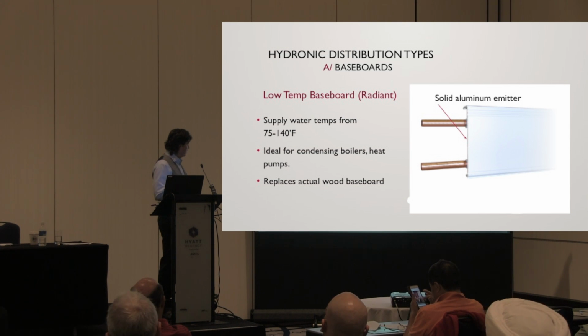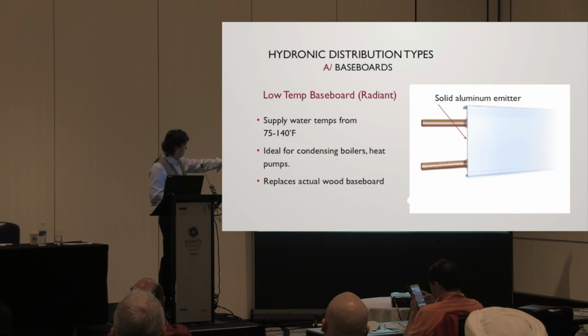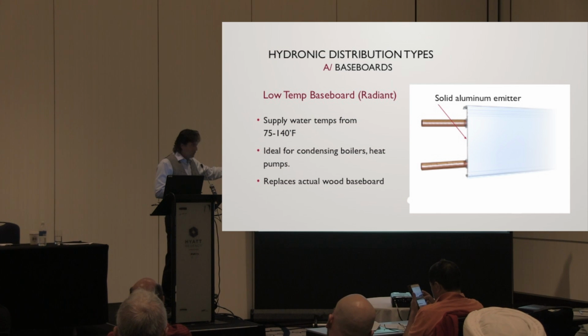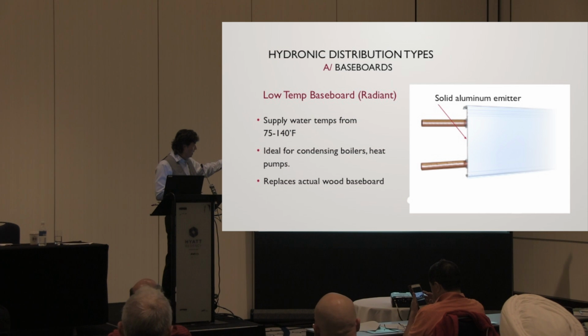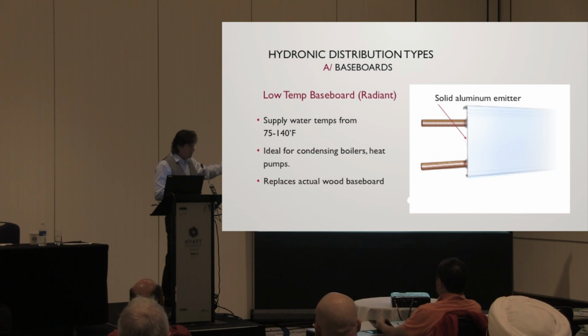And then you got these rascals here. I don't know if you've seen these. These are made of solid aluminum, actually. Very low water temperature, so it's a good match with heat pumps, which produce low water temperatures, or condensing boilers, which love low water temperatures. But this is actually meant to replace the baseboard itself. So this is painted sort of white the same way baseboards are. I'm sure you can paint them as well. They have corner connecting units, and they actually offer a lot of heat. And truly that is now more of a radiator than a convector.